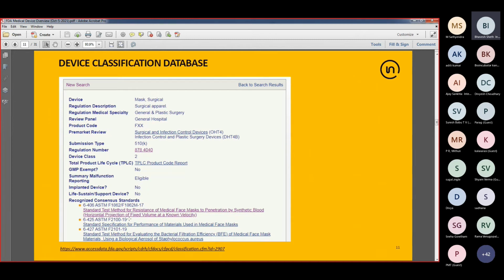Now you see a lot of recognized standards. So these are some standards that FDA tends to indicate on the classification page itself. My take on this is that this list is never absolute. You cannot solely rely on this list. And I'll give you an example for this. If you look up a ventilator product code and you look at a similar classification page, you will see some standards mentioned, but you're never going to find the basic general electrical safety standard, which is IEC 60601-1, or the general EMC standard, which is IEC 60601-1-2. Now, does that mean that you don't need to comply with that standard? Absolutely not. So that's why you should use the information on this page about the standards as a guideline rather than an absolute complete list of requirements you need to meet.